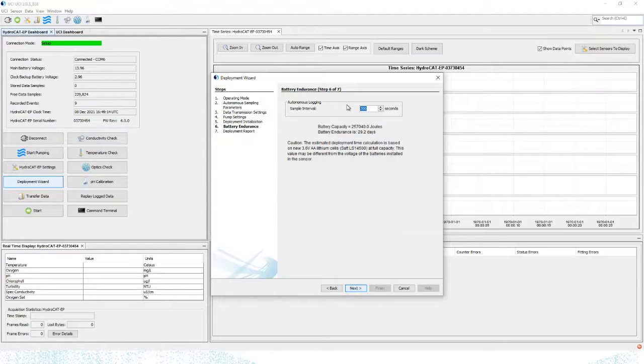Remember, you want to replace your pH sensor every 90 days anyway, so if you are doing a 900-second interval, you might consider changing that to something shorter so the battery endurance is approximately 90 days. That way you can go visit your instrument, replace the battery pack, and replace the pH sensor at the same time in a single visit. That's a good way to be efficient.